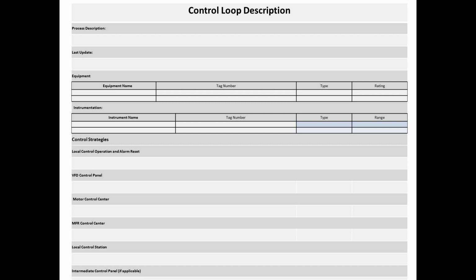And then we talk about the control strategies, which are the various different methods of control. There's a local control station, and this area explains what's located on the local control station. There's a local-off-remote control switch, and there are on and off push buttons. Under this section, you would talk about the local control station. In order to operate, the switch needs to be in local. The on push button will start the piece of equipment, and the off push button will stop it. So that gives the programmer knowledge of how they need to program that. They need to allow for that to happen.